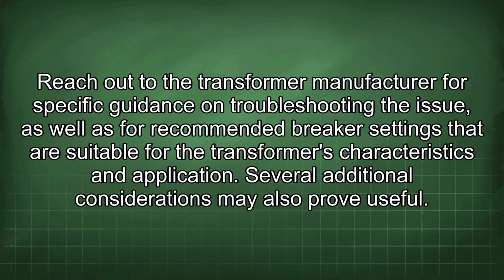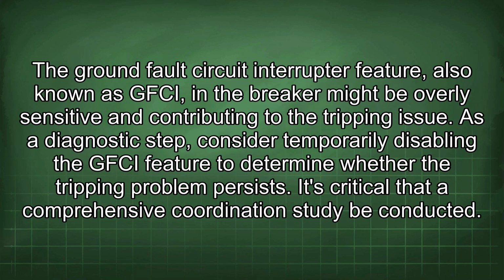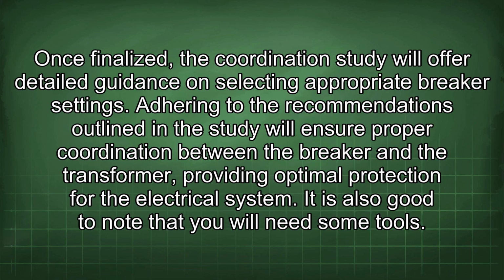Several additional considerations may also prove useful. The ground fault circuit interrupter feature, also known as GFCI, in the breaker might be overly sensitive and contributing to the tripping issue. As a diagnostic step, consider temporarily disabling the GFCI feature to determine whether the tripping problem persists. It's critical that a comprehensive coordination study be conducted. Once finalized, the coordination study will offer detailed guidance on selecting appropriate breaker settings. Adhering to the recommendations outlined in the study will ensure proper coordination between the breaker and the transformer, providing optimal protection for the electrical system.